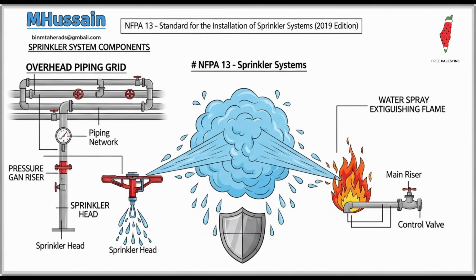Okay, let's transition now to the highlights of the 2019 edition itself. These are the key updates you should probably know about to understand where the industry has moved recently. The first major change really addressed freeze protection in non-heated environments. Historically, the requirements for protecting piping were, well, highly prescriptive. Do this, use this specific material, apply this exact insulation. But the 2019 edition introduced a new allowance. Engineering analyses are now explicitly permitted to support alternate freeze protection schemes. And that represents a pretty significant shift, moving away from just prescriptive rules towards more performance-based flexibility.